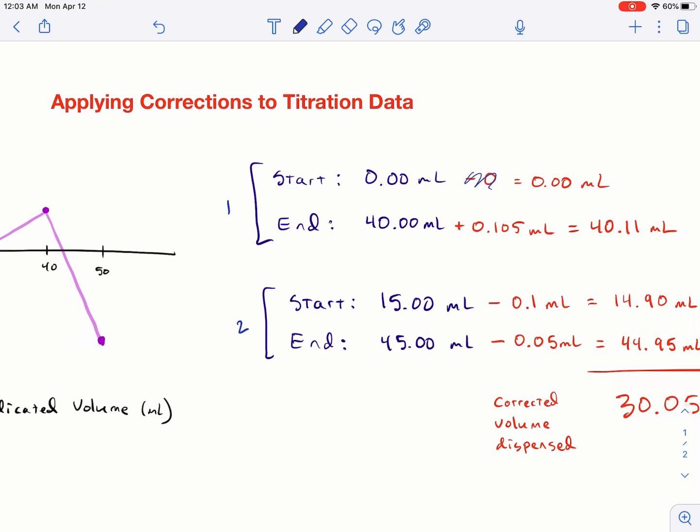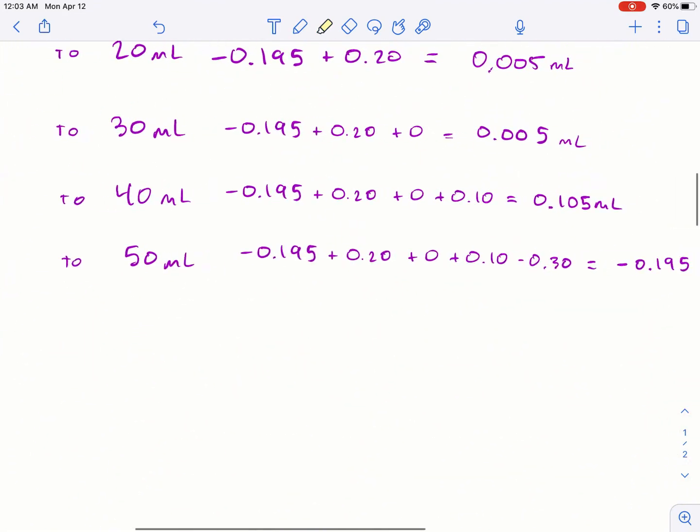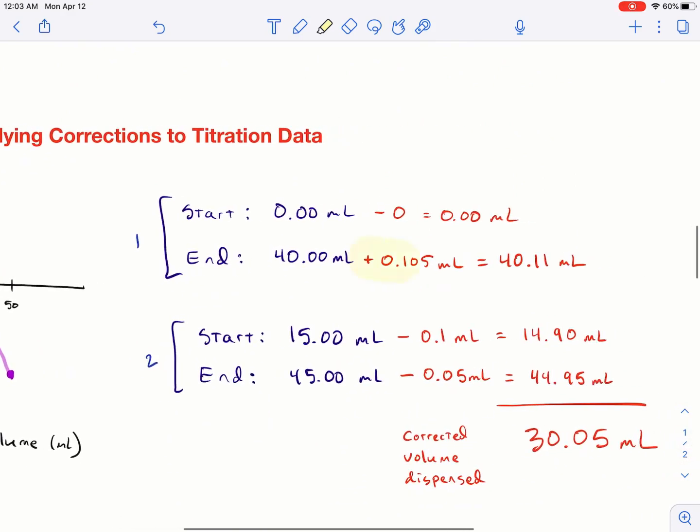Zero doesn't really have an adjustment, so whatever, so you're still at zero. And then 40 milliliters does have an adjustment. You can pull it off the chart or you can use your data up here. 40 milliliters, my cumulative adjustment is 0.105. It's positive, you add 0.105 to it. And then here's your final volume. And then for this titration, when you want to find the amount dispensed, it's just 40.11 minus zero. So this would be your amount dispensed. That's the calibrated answer.